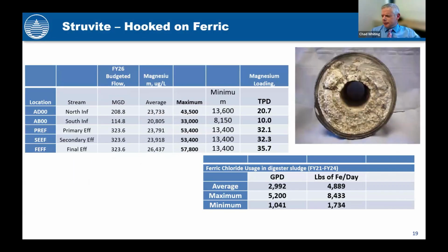So next we'll talk about struvite, and Deer Island is hooked on ferric. Struvite is a magnesium ammonium phosphate compound that forms hard scale on the inside of pipes that is almost impossible to remove. As you can see from the photo in the top right, that is an overflow line from one of our digesters, almost completely blocked with struvite. The MWRA service area serves a number of coastal communities with I&I challenges, contributing to the high concentrations of magnesium that you see in this chart, 20,000 to 57,000 micrograms per liter coming in our influent. This adds to that formula to help form that struvite, and it accelerates that process, where other treatment plants that are not coastal wouldn't have as much magnesium to start forming that struvite.